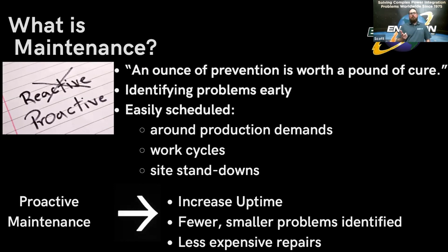That reminds me, there's one site that I went to, a casino, that was in their crisis management mode of doing maintenance and ended up destroying a generator because they hadn't properly performed any maintenance for several years. That ended up costing them a generator plus all the downtime for their facility. The site guy was telling me that it was in the range of millions of dollars per minute while they were down. So I thought that was a poor decision on their part.